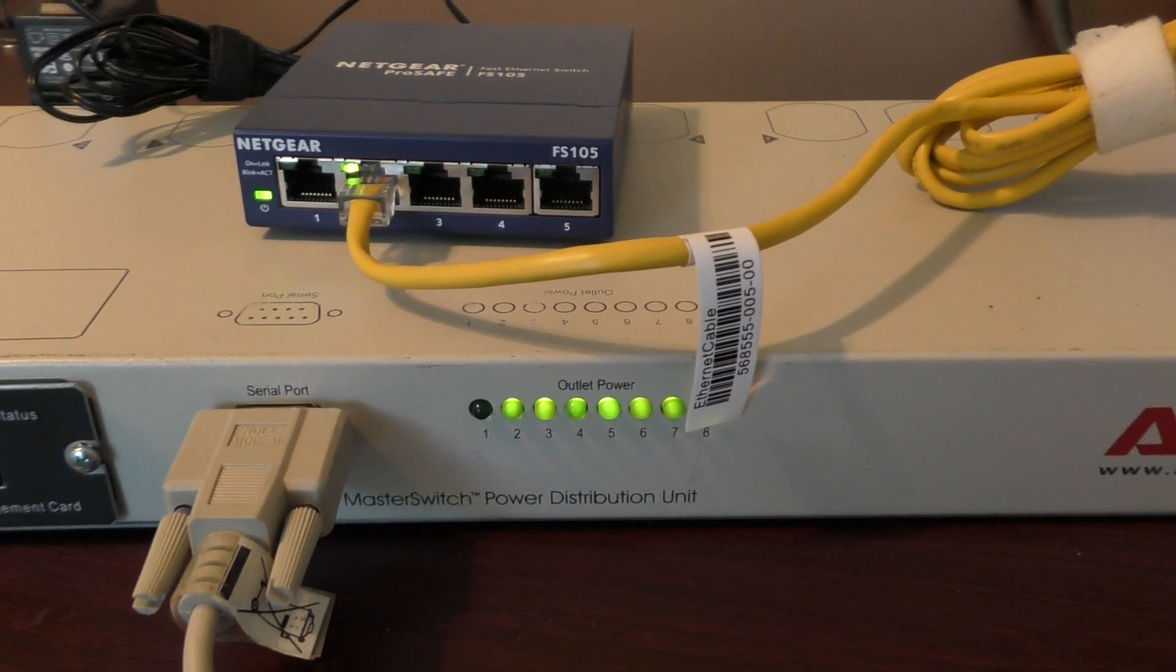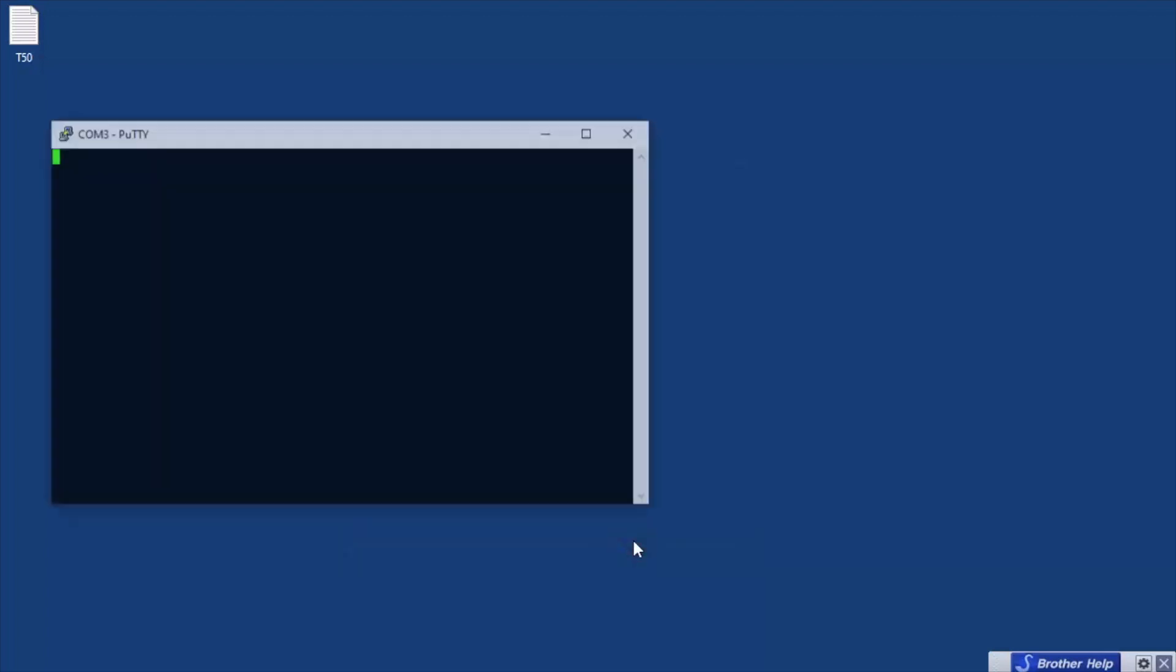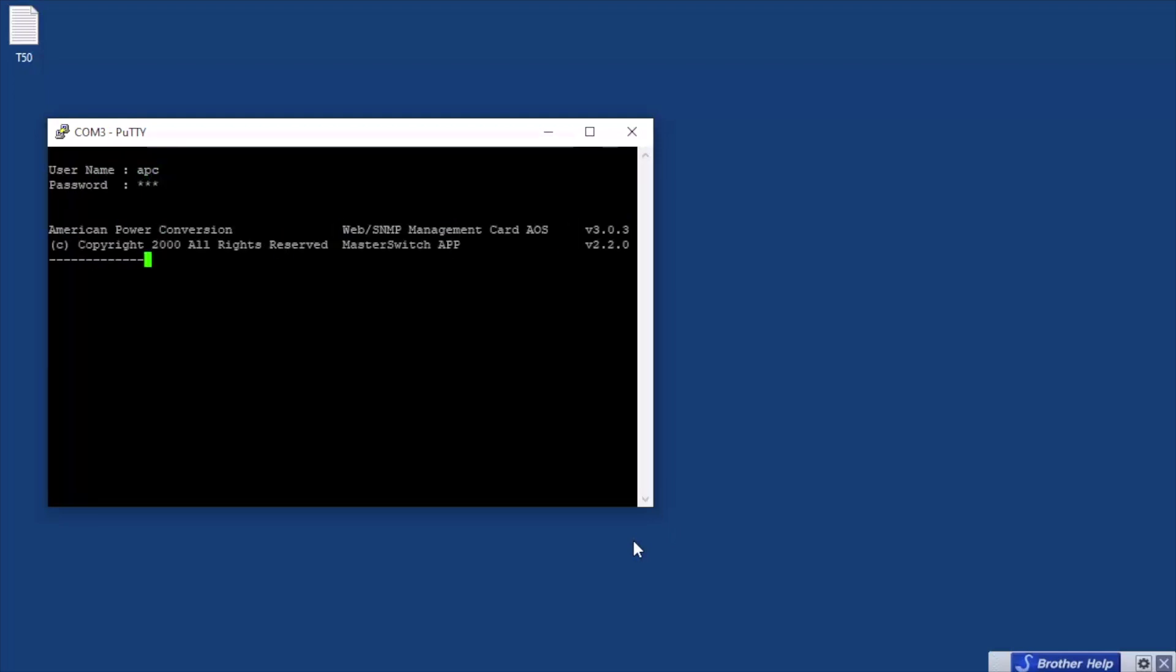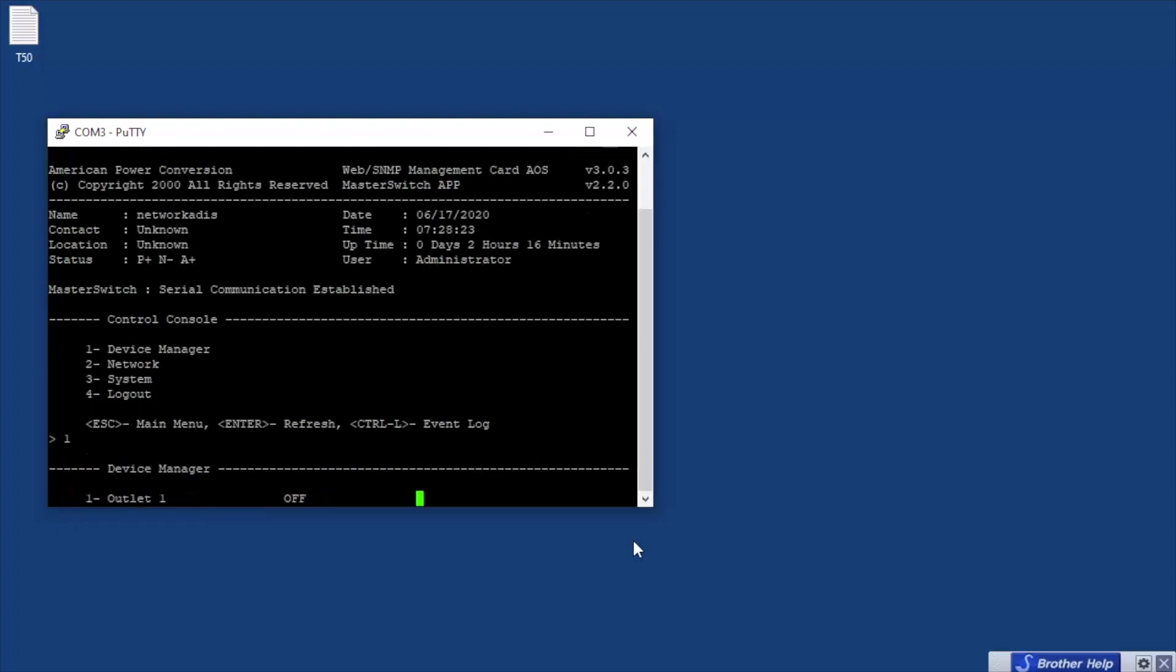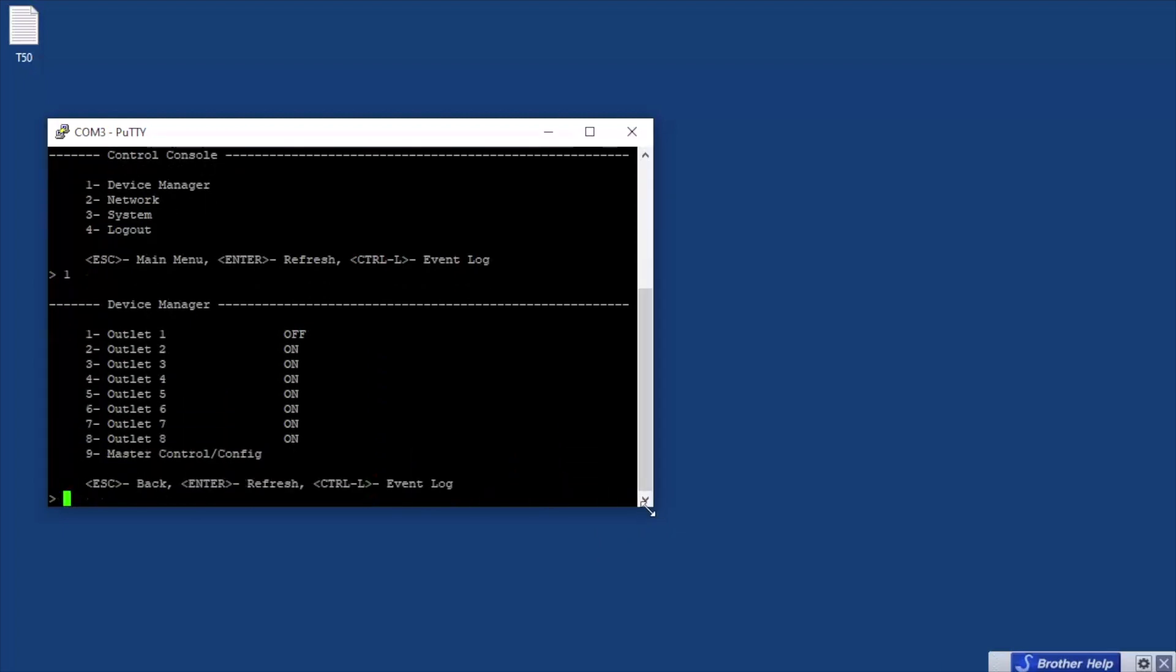All right, so let's go over and take a better look at the menu. I'll show you some of the things that are in the menu. All right, so just a few minutes to take a look at the console options. I use putty to connect to this with a null modem cable. Take a look at the speed - 2400. You know, a lot of things are using 9600 by default, but 2400. Anyway, if you get this thing defaulted, the username and password is APC lowercase, so APC and then APC. Let's see, so you've got most of what you want to do in terms of outlet control happens in the device manager, so option one there.